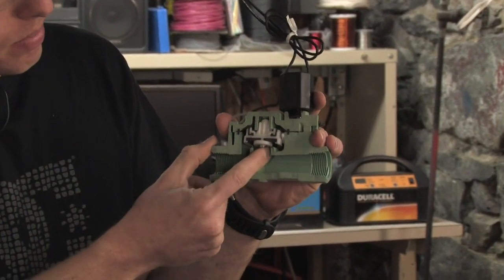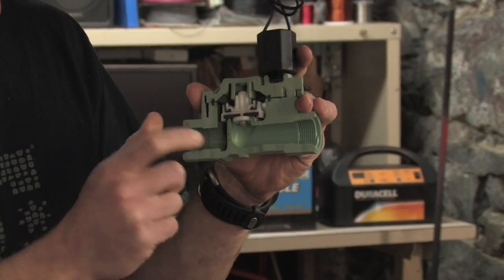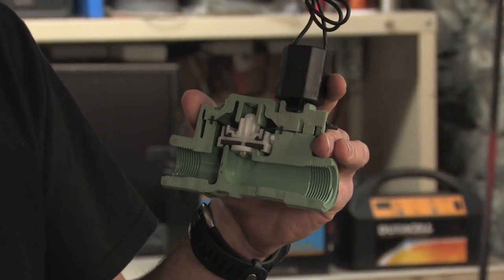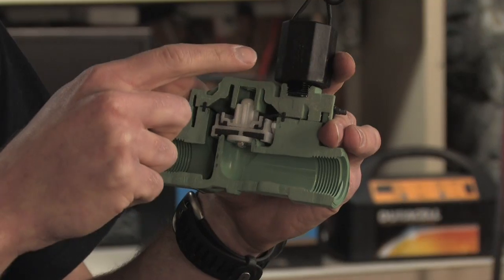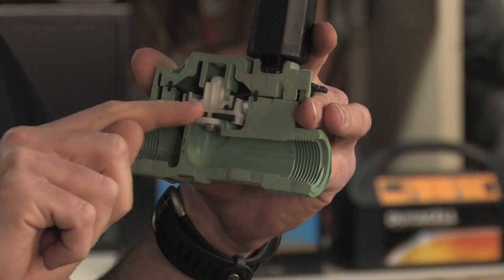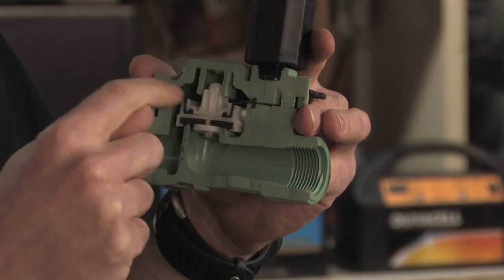Up against this little rim, stopping the flow of air through the valve. How this works is this solenoid here lifts a little plunger, which you can't see, and it allows air to escape from this upper area.